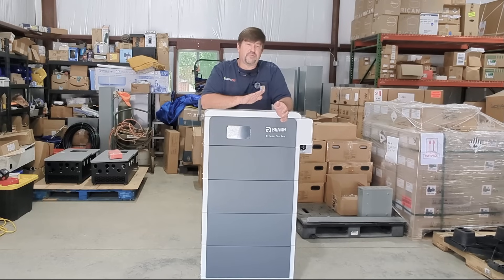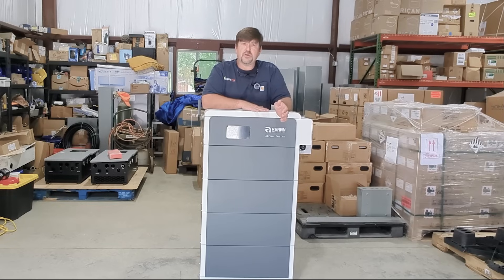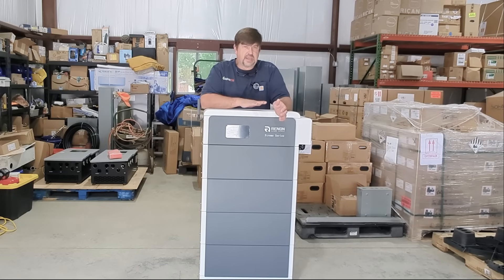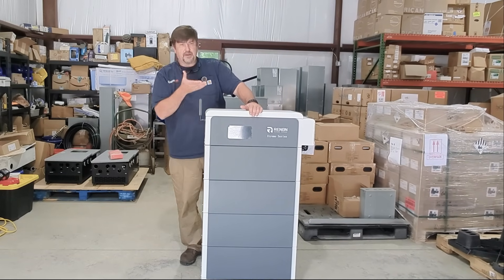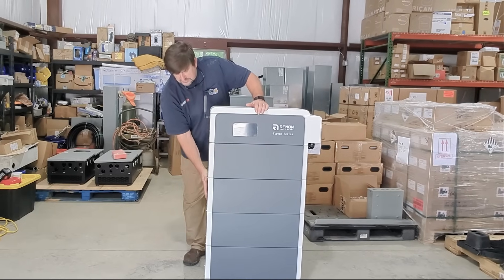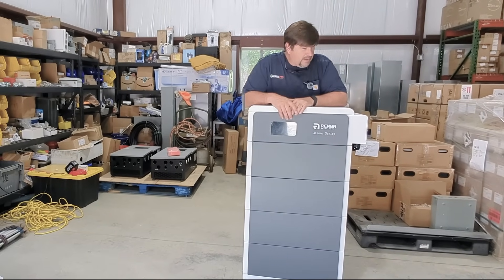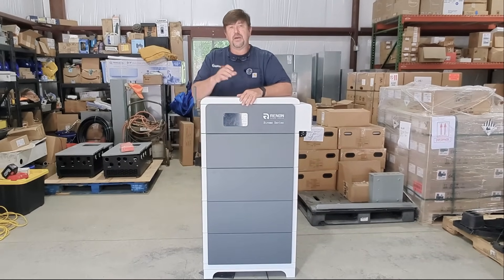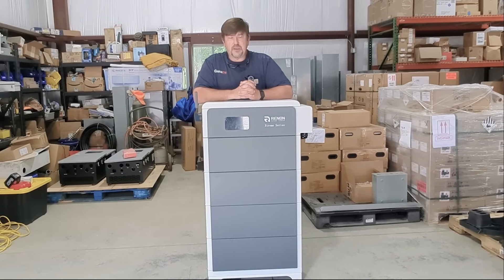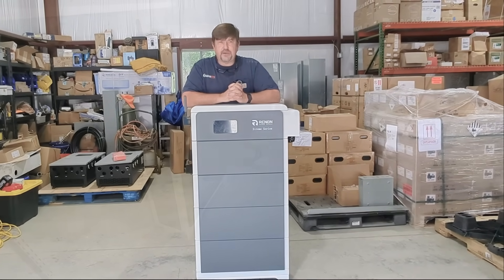How do I deal with a time-of-use rate? How do I lower my power bill when this demand charge is killing me? This is a solution. It's a very reasonable battery - you can find the link and cost in the description. It's scalable up to eight batteries. We're putting four modules on a 15k, which should be enough to zero out his demand charge with his utility. That's what he's after.